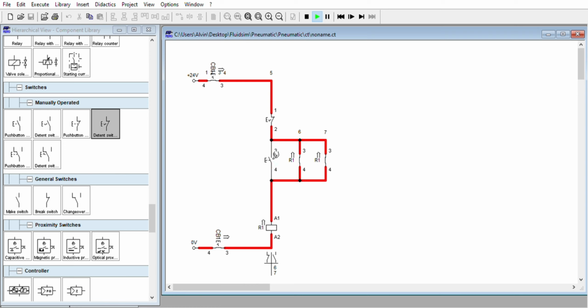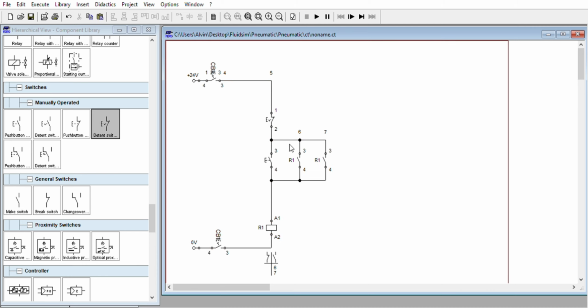So this one is useless anymore, the push button, because once you turn this on, there are three independent paths. One is here, one is here. So if the pressure is released here, of course you are going to release that one, because you are not going to turn that on forever. Otherwise, that is not a correct start-stop operation. So that's why we need the holding contact, latching contact, or sealing contact. How are you going to say it? But that is redundant. So we can use this one for another purpose.